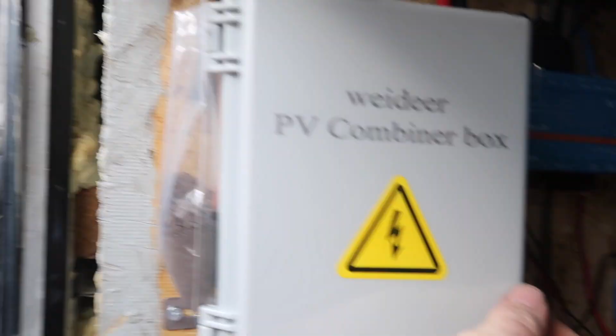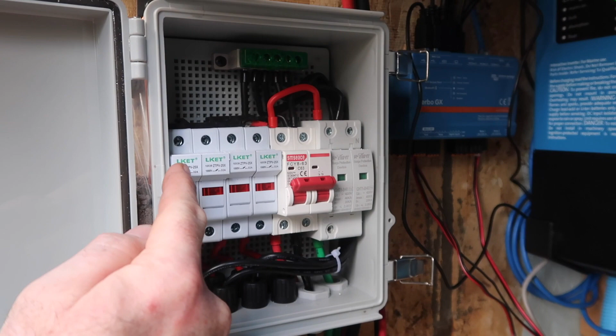Inside of here is your photovoltaic disconnect. Some important things to consider: these are your fuses for all 4 strings of panels you have on your roof. Never ever open these up under any kind of load — if it's sunny out and you're getting any charge, do not ever open these, you could get a big arc flash. Use the switch first to remove any loads, and then you can change things if you have to.